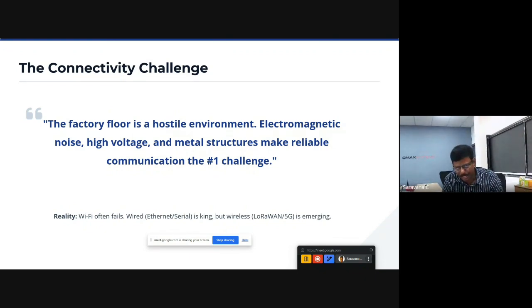Last week I went to a big factory with multiple huge workshops and sheds, and they wanted to collect data from all the sheds and display it in the office. We were thinking about using LoRaWAN, but because the entire building is made of steel structure - sheet metal or steel sheets - that makes like a Faraday cage, and the RF won't go out of the sheet. So we suggested they use a wired network.